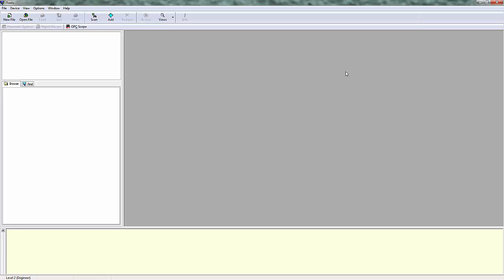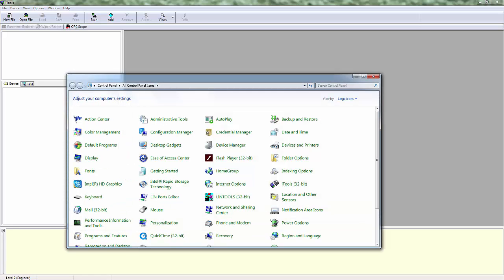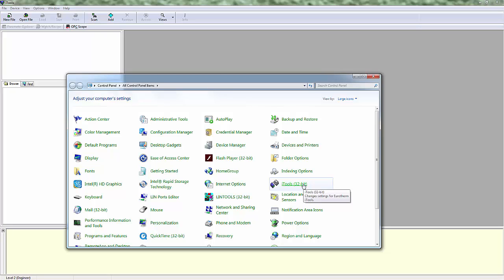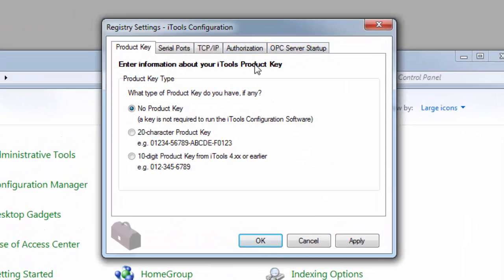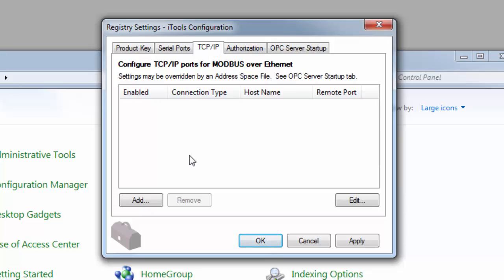From a software side, we need to tell iTools how to scan for the device. There are two ways to do this, and it's really based on preference. The first way is through the Control Panel. Once iTools is installed, it puts an icon into your Control Panel called iTools 32-bit. Click on it, you'll get a pop-up — hit Yes, it's to do with user access controls. Then look at the TCP/IP tab. Here is where you can add various IP addresses so that iTools knows what to scan for on the network. This is a one-time setup — once you do it, you won't have to do it again unless you add another IP address.